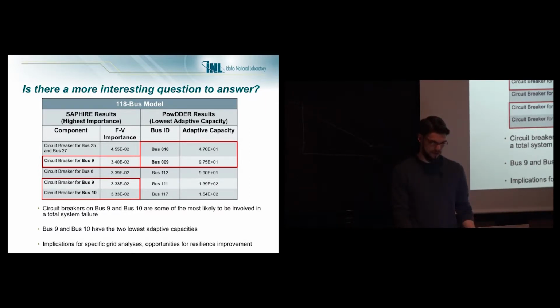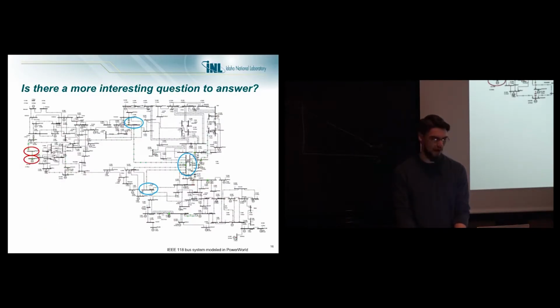So what does this mean? I showed this graphic before with no circles on it, asking what components need to be improved. Well, buses 9 and 10 are in red—those can't adapt well to voltage instabilities, and the circuit breakers on them, if they fail, are likely to lead to system-wide failure. The blue circles are circling other components in the system that, if failed simultaneously with the circuit breakers on bus 9 and 10, lead to system-wide failure.